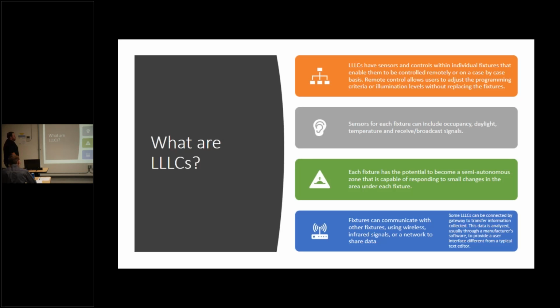So here's kind of the 4 basic components that you need to have a light fixture be qualified as LLLC. They have to have sensors and controls within the individual fixture that can be controlled remotely or on a case-by-case basis. Sensors for each fixture need to include occupancy, daylight, temperature, and receive or broadcast signals. Those are the 4 basic ones you're going to see. It's not limited to those, though. Each fixture then has the potential to become a semi-autonomous zone that is capable of responding to small changes underneath each fixture. Fixtures can then communicate with other fixtures using wireless, infrared signals, or a network to share data. Some LLLCs can be connected by gateway transfer, so that way you can actually compile the data and run algorithms and see trends that are happening within the building.